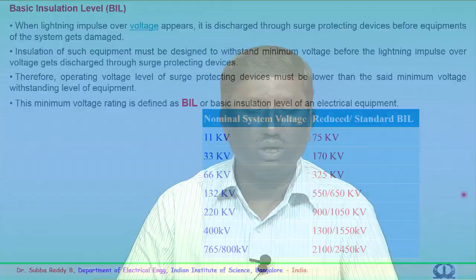Before going to that, it is important to know what the basic insulation level is. The basic insulation level, or BIL, is a very important terminology which we have to adhere to, and the equipment manufacturers or the utility personnel are to know the basic insulation level of any equipment. How it is done: it is assumed that when a lightning surge or lightning impulse, the 1.2 by 50 waveform, is impinged on any equipment, an over voltage appears across it. This lightning impulse over voltage is discharged, as mentioned earlier, through surge protection or lightning protection devices before equipment of the system gets damaged.